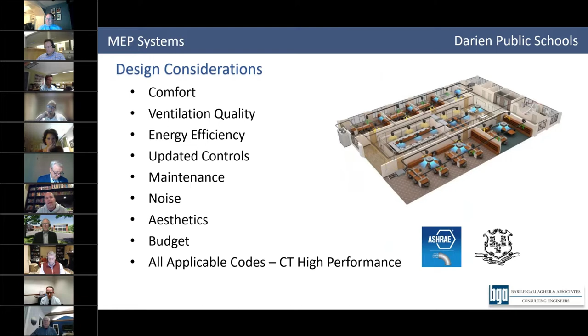Sure, there's a slide later on. One thing we're doing is using 100% outside air energy recovery systems just for ventilation - tempered ventilation - so the ductwork gets very small. If you were air conditioning with air, the amount you'd have to move is huge, so ductwork would get very large. That's one strategy. The 40s wing has very high floor-to-floor heights, so we'll have room in the ceilings for terminal cassette units in each space, giving individual control, and then you're just running refrigerant piping, which is relatively small compared to ductwork.